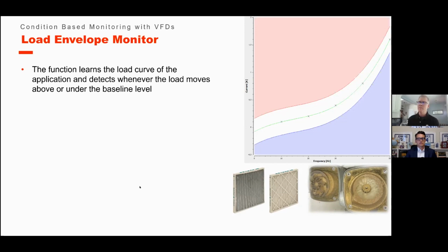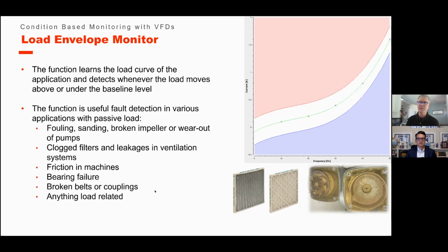So it's really useful in fault detection, especially even with passive loads. A lot of times you want to know if you're having bearing failures, if you've got broken belts or couplings, if you have broken impellers in water pumps, or you're fouling them or wearing them out, because the actual blades will wear out in there. Or if you have clogged filters and leakages in piping in systems. So having that information on the load, anything that's load related, this will give you an envelope of a high limit and a low limit. Very important for both limits. You want to know if you're overloaded. You want to know if you're underloaded, because there are problems in both conditions.